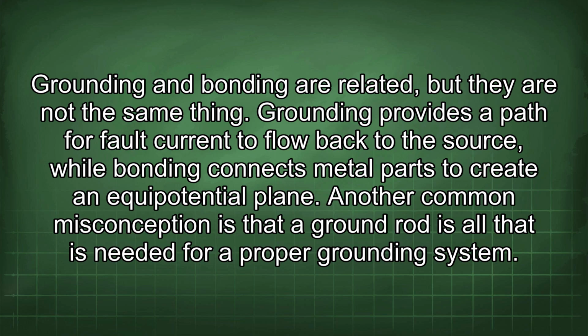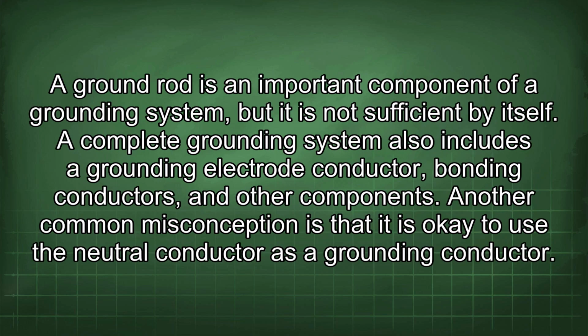Grounding provides a path for fault current to flow back to the source, while bonding connects metal parts to create an equipotential plane. Another common misconception is that a ground rod is all that is needed for a proper grounding system. A ground rod is an important component of a grounding system, but it is not sufficient by itself. A complete grounding system also includes grounding electrode conductor, bonding conductors, and other components.